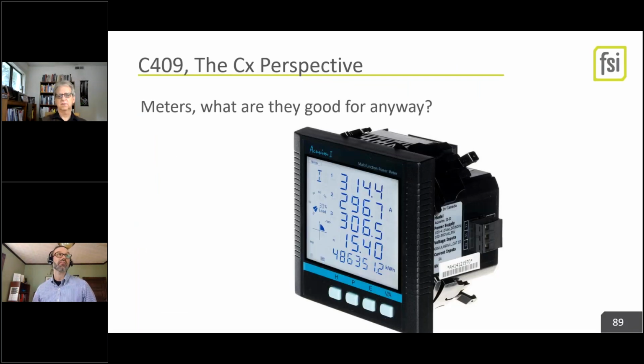For the most advanced buildings we work on, we have in-depth energy meters on everything, but the code only requires that you meter by subtype. So you could put a meter on all the lighting if you break out your panels correctly, and all the plug loads, all the HVAC. You don't have to have meters everywhere, although they're really helpful if you're trying to troubleshoot why you're using more lighting power this year than last year - that's fantastic data for us data geeks who want to get deep into it and tune the building.